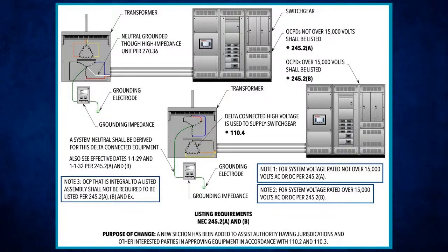Now, if it's an overcurrent protection device for systems rated over 15,000 volts AC, when I get into this, it says they're required to be listed, but the listing requirement for that overcurrent protection device is not effective until January 1st, 2029.